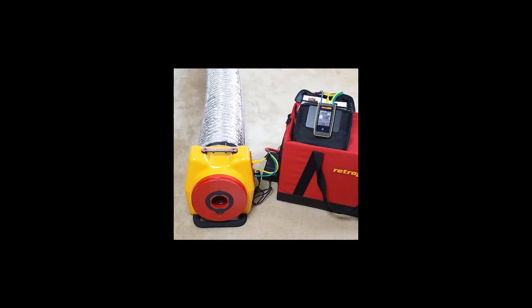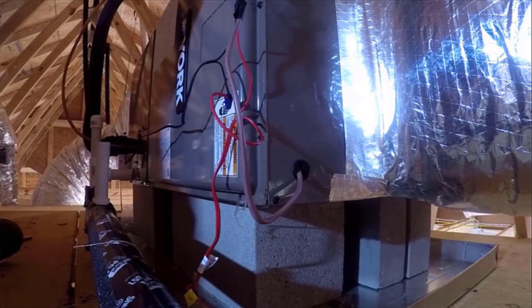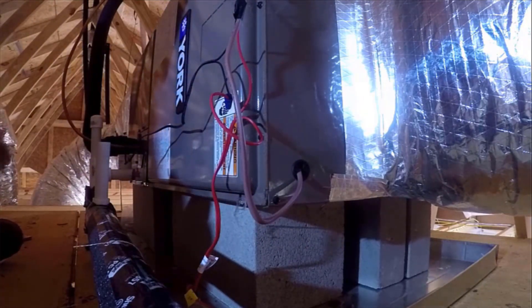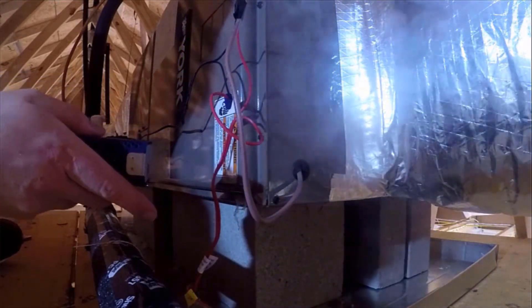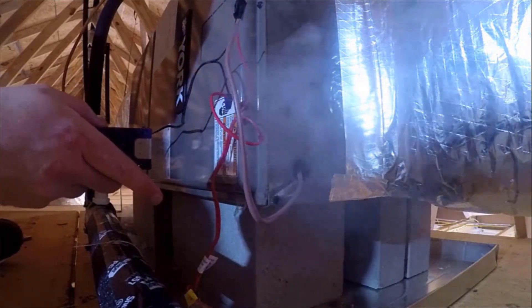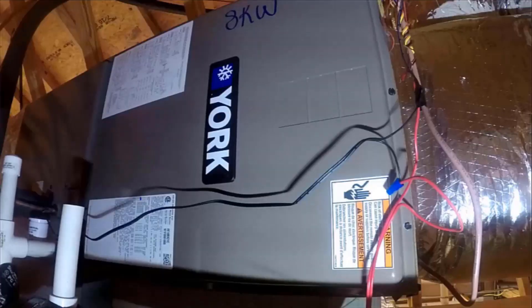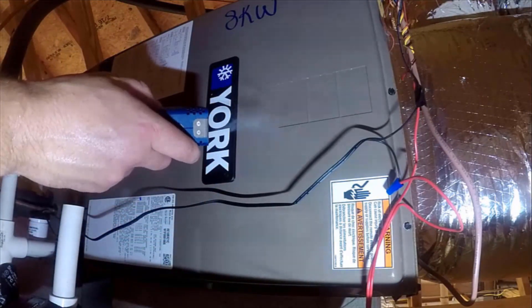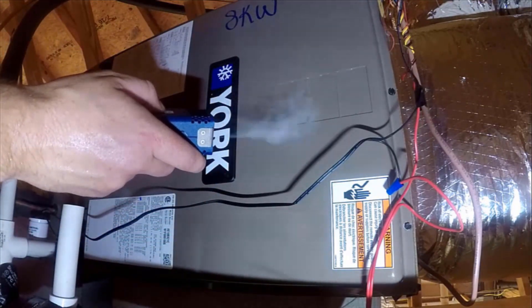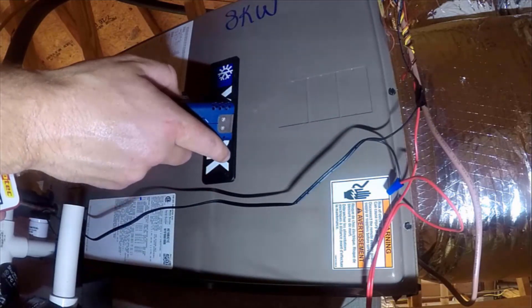Looking at duct systems, we are pressurizing this duct system with the Retrotec duct tester. Here we're looking at some penetrations in the air handler where those can be sealed to make the system more efficient and to keep air from leaking out. You can see how the smoke is interacting there, along with these punch-outs on the side — these are usually sources of leaks as well. You can see the air getting pushed out of that air handler interacting with the smoke, showing us that we have a leak.